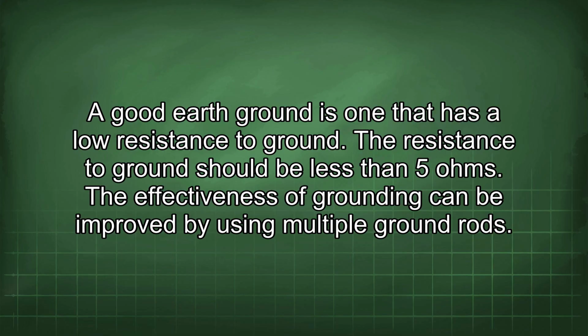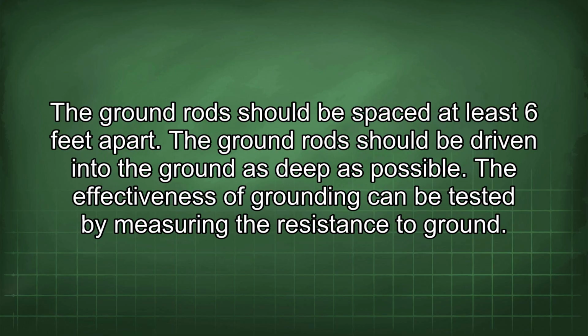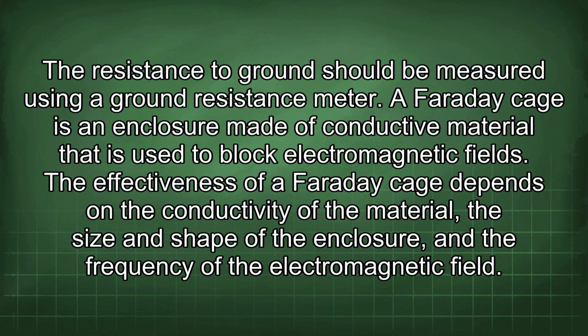The effectiveness of grounding can be improved by using multiple ground rods. The ground rods should be spaced at least 6 feet apart. The ground rod should be driven into the ground as deep as possible. The effectiveness of grounding can be tested by measuring the resistance to ground. The resistance to ground should be measured using a ground resistance meter.